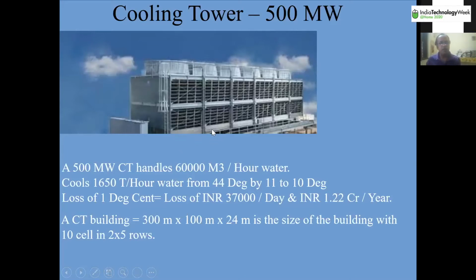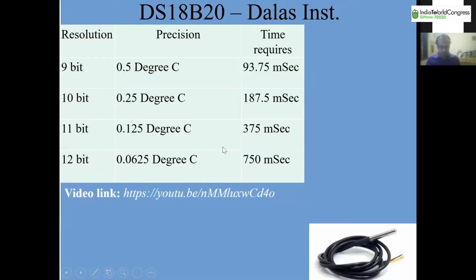So there, in one look, he can find out which cell is malfunctioning. And we have put not one, we put 5 temperature sensors per tower. So for 10 cells, 50 sensors we used up. Let's see how. There are a variety of DS18B20s available, and this is the variety we have used. This is metal encapsulated and waterproof, because cooling tower water, it is only water and steam. So these sensors have to be waterproof, otherwise corrosion will take place.